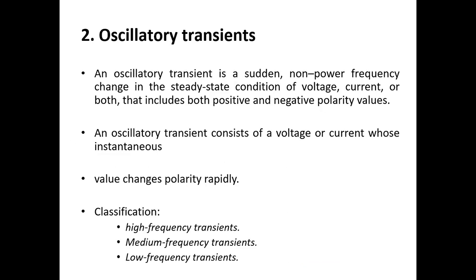Now, what are oscillatory transients? An oscillatory transient is a sudden non-power frequency change in the steady state condition of voltage and current, or both, that includes both positive and negative polarity values. An oscillatory transient consists of a voltage or current whose instantaneous value changes polarity rapidly. By classification, high frequency transients, medium frequency transients and low frequency transients are all called oscillatory transients.